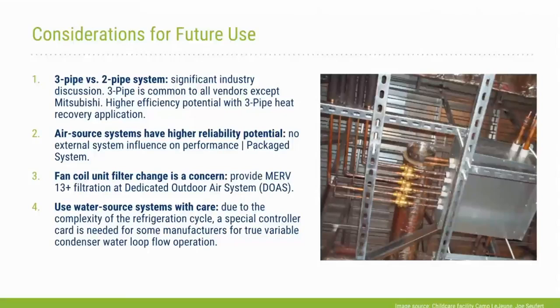One thing we did realize on this project that's very interesting in working with the manufacturer is that because there is still a separate condenser water loop, in this particular case it was tied to a ground source heat exchanger in a parking lot adjacent to the building. That is a component that is not directly controlled by the VRF control system. In that case, it's controlled by the building automation system. So there's a potential for some integration challenges with how those two react to each other, while when using an air source system, all of the controls are completely packaged, integrated together, and optimized by the particular vendor.